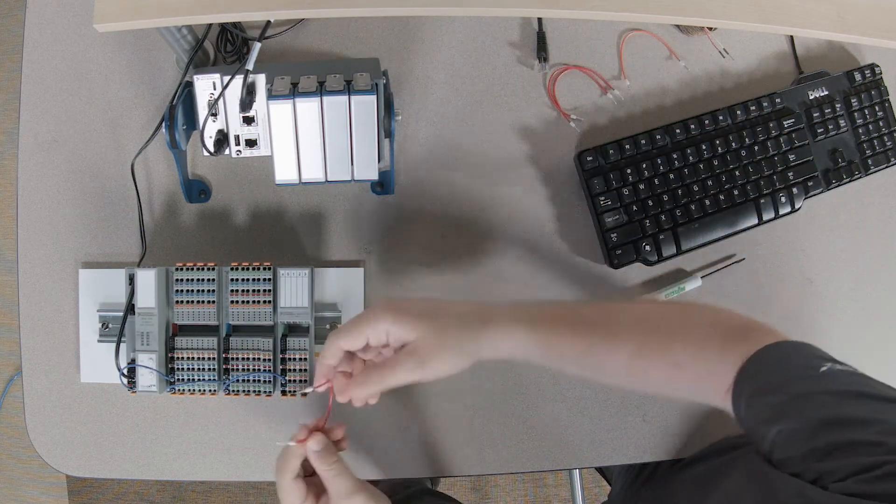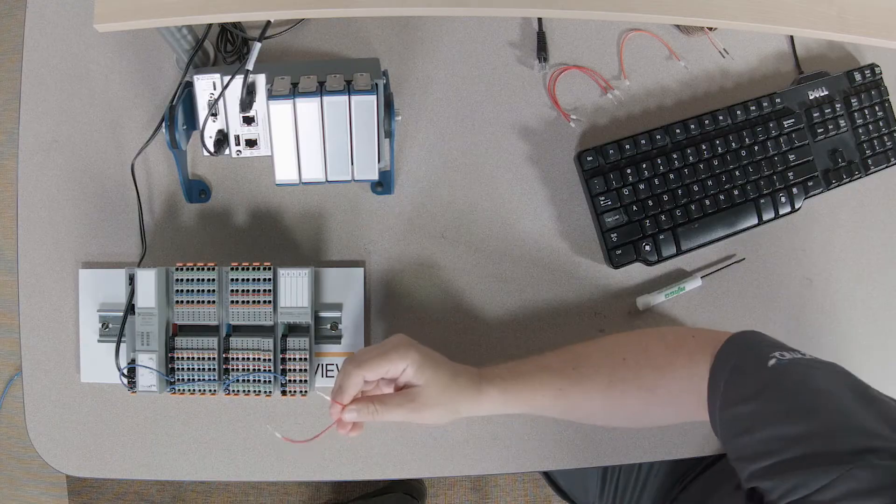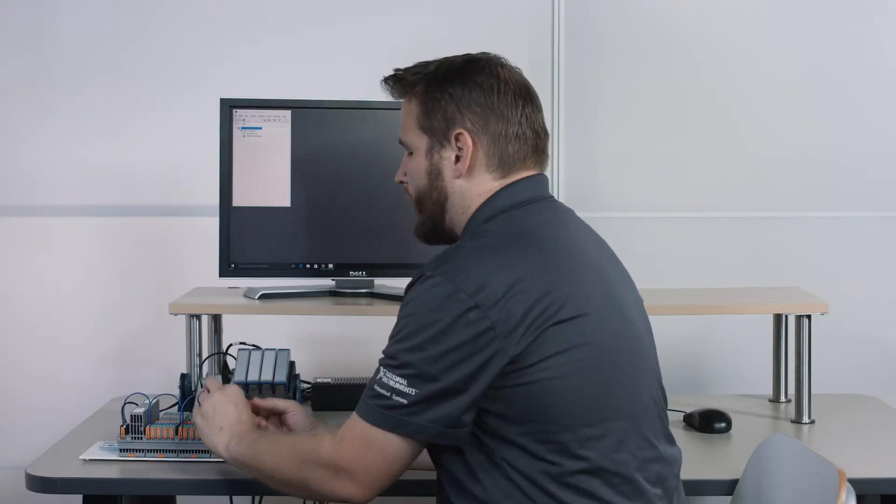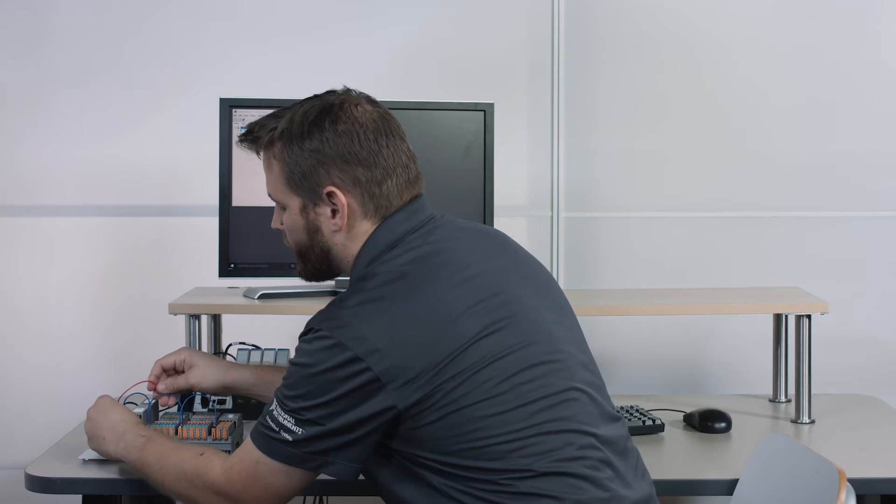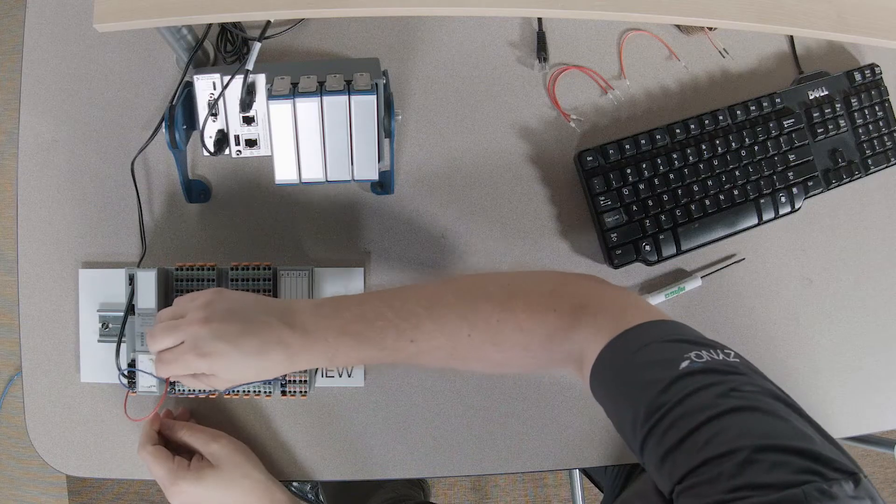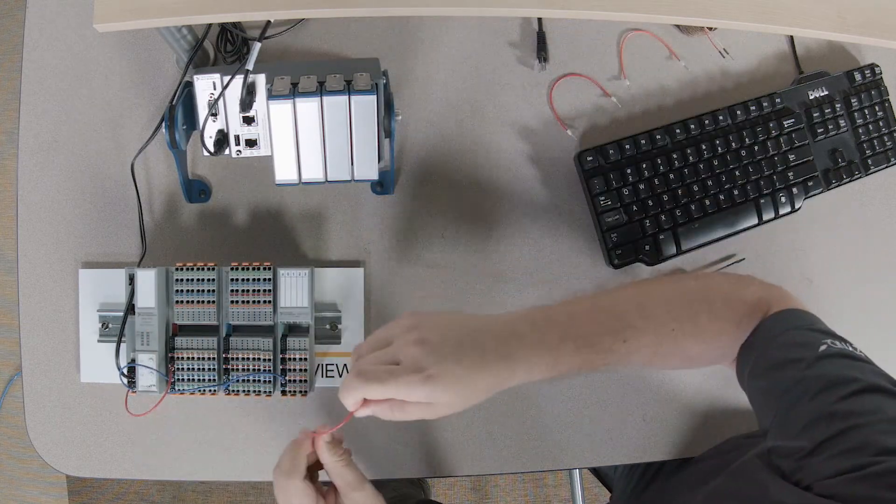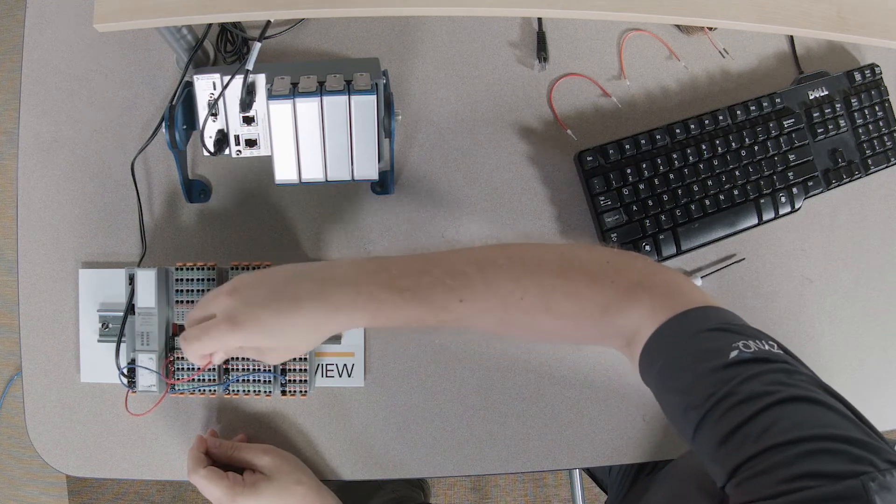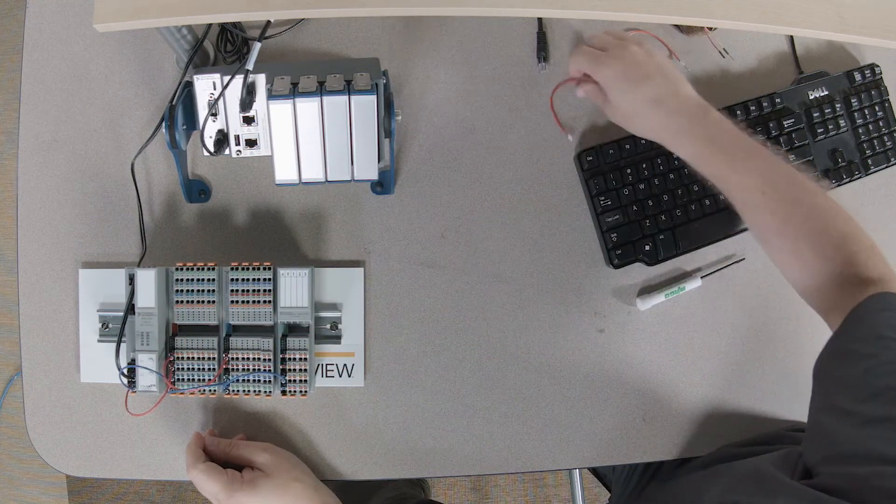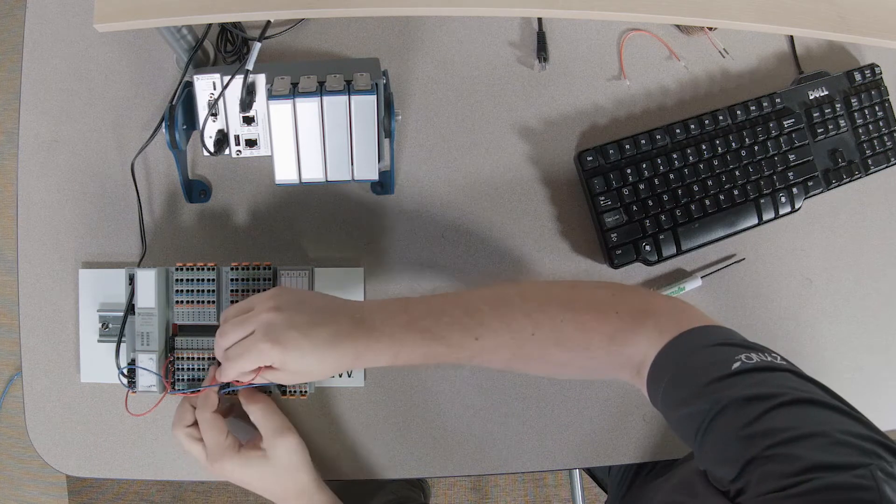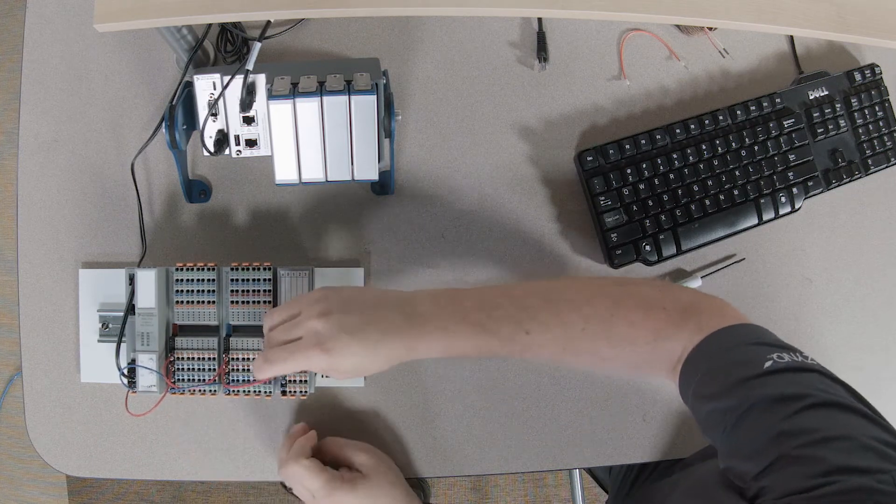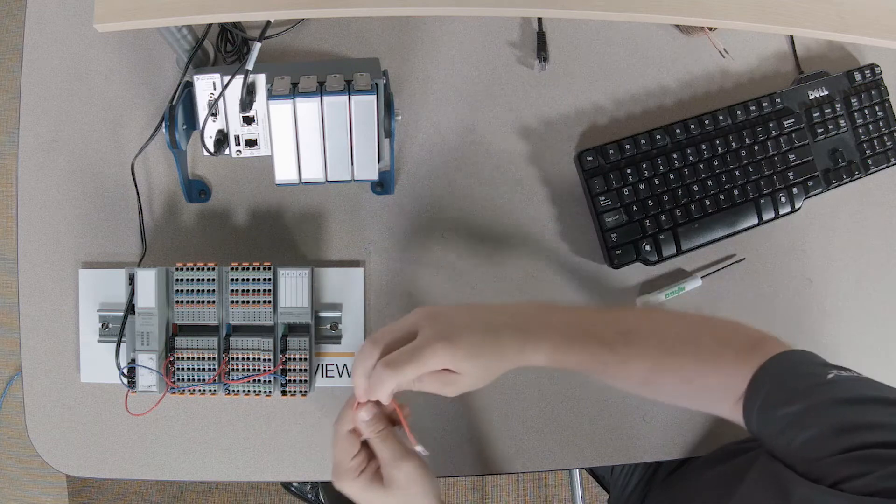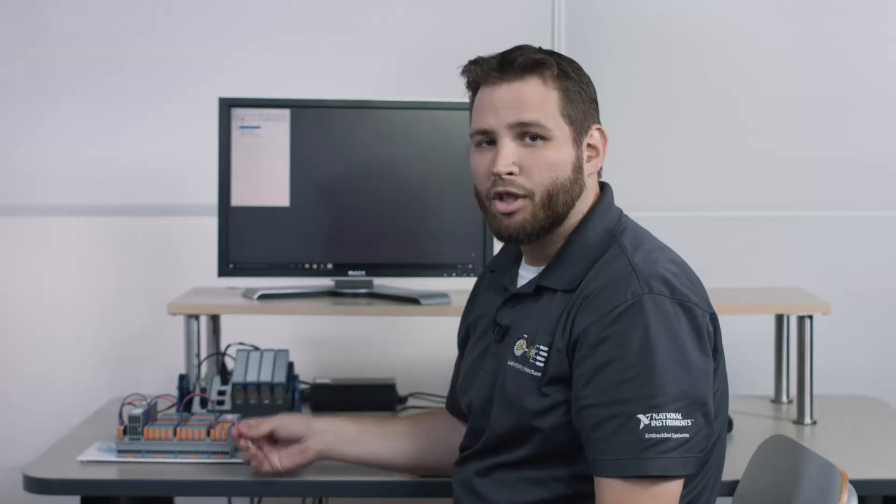All right, other thing I want to call out, you'll notice that I'm using stranded wire with ferrules on it. And I'm not using any tools to attach this. This has something called push-in technology. So, I can just take the conductors and push them right into the connector. To take it off, you do need a screwdriver, but you just press the little connector above the conductor as it pushes in. Now, also, for our application, I'm going to go ahead and jumper the digital output zero to digital input zero.